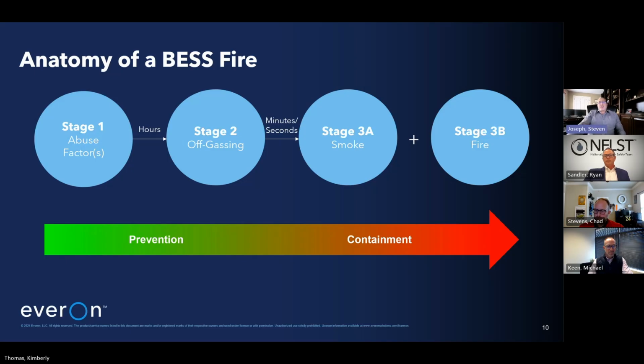Again, as I said, as the cells fail, they create this exothermic reaction, which begins the stage 2 process. And then as you have these elevated temperatures, cells obviously will begin to swell and ultimately vent gases. And those gases are detectable using gas detection technologies specific to the vent gases that are present. And from our experience in education and research surrounding battery energy fires, VOC sensors are ideal at this stage, as they can detect a host of gases relevant to the gases typically present during the stage of development.